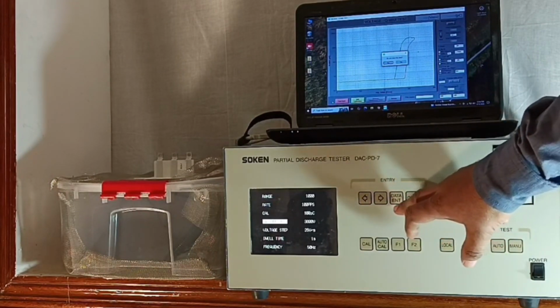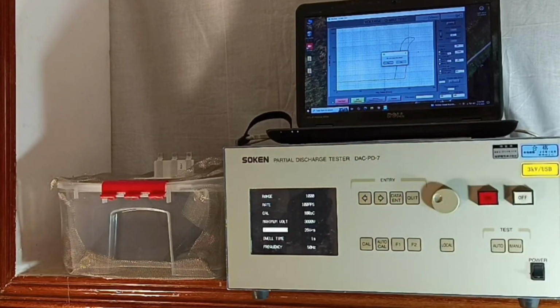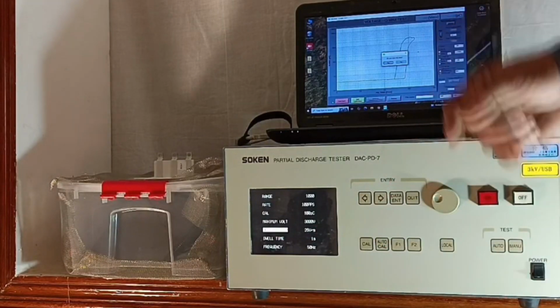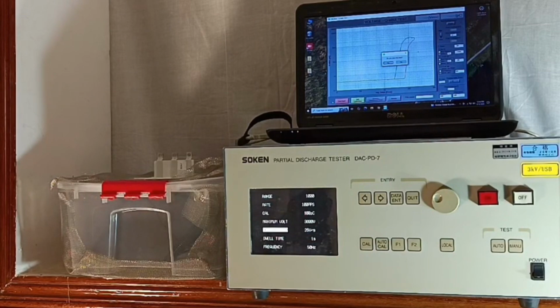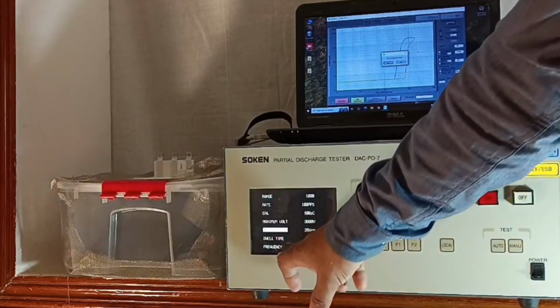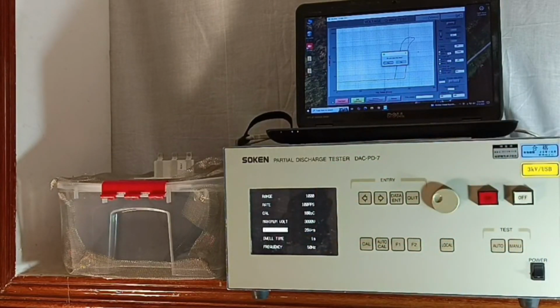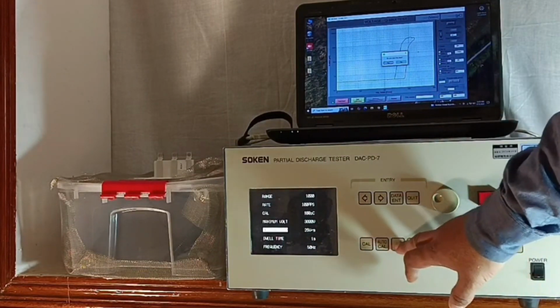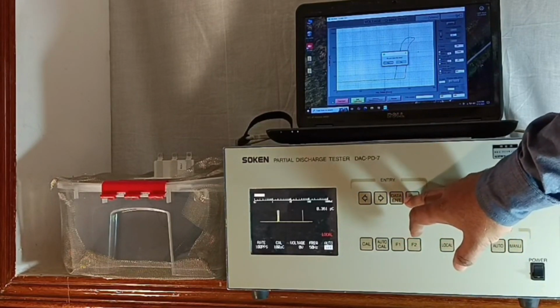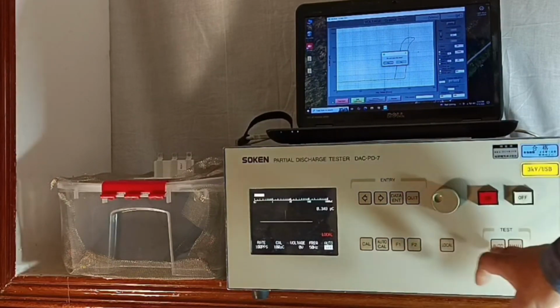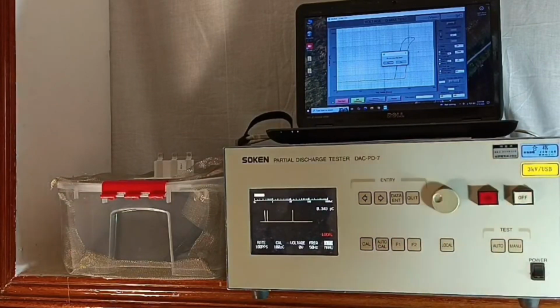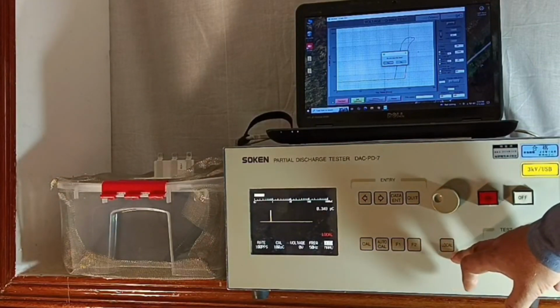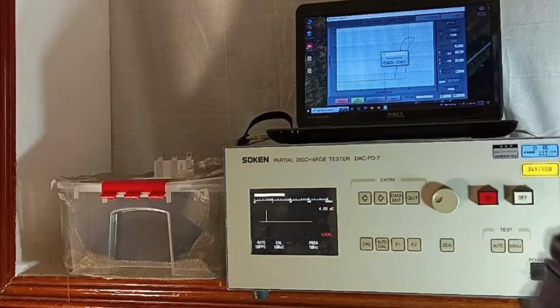So then next is voltage. Here you have 25 volts, 50 volts per second. But in the PC you can even choose 10 volts per second. Dwell time is a hold time. If you want to test, then the frequency you can select the 50 hertz or 60 hertz for the source frequency, which is independent of the main supply. This is manual mode and auto selection. You can go and you can see the auto cal or manual cal.